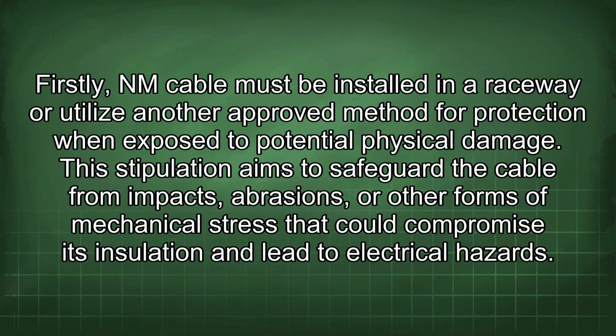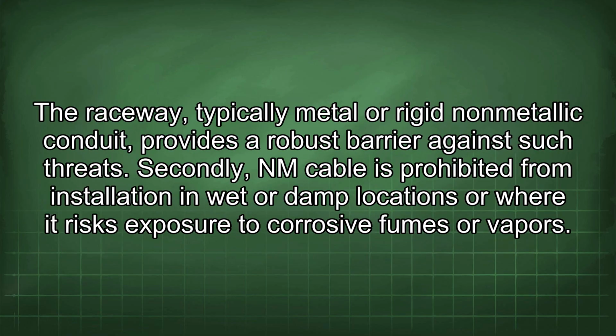Firstly, NM cable must be installed in a raceway or utilize another approved method for protection when exposed to potential physical damage. This stipulation aims to safeguard the cable from impacts, abrasions, or other forms of mechanical stress that could compromise its insulation and lead to electrical hazards. The raceway, typically metal or rigid non-metallic conduit, provides a robust barrier against such threats.